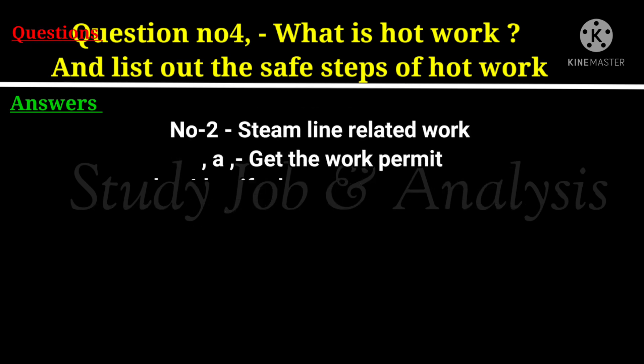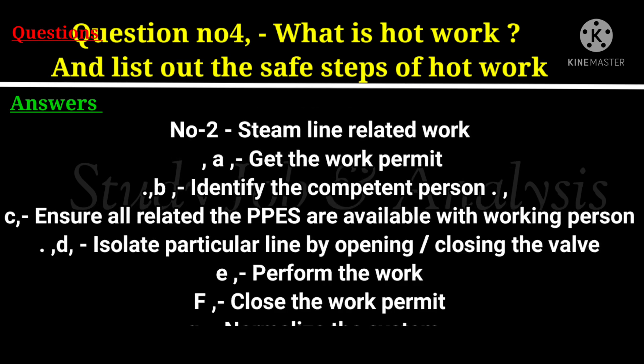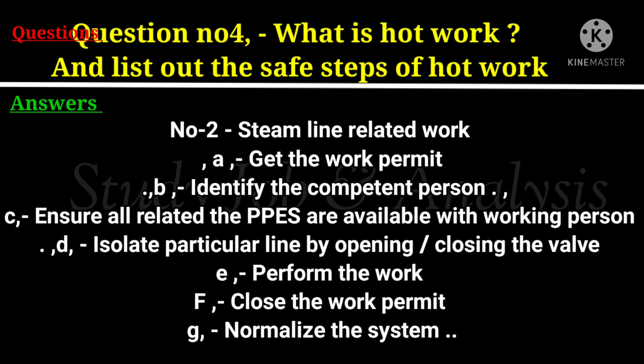Number 2: Steam line related work. A. Get the work permit. B. Identify the competent person. C. Ensure all related PPEs are available with the working person. D. Isolate the particular line by opening or closing the valve. E. Perform the work. F. Close the work permit. G. Normalize the system.